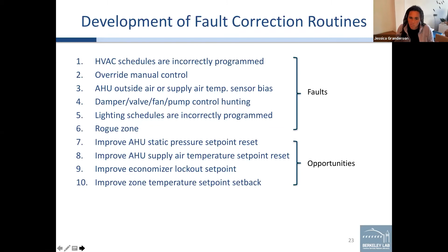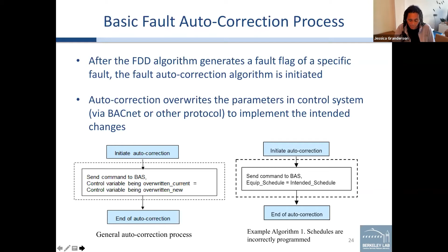This is just a schematic of what that process looks like in a sort of coded environment. The FDD tool finds a problem, raises a flag, which then triggers the correction routine to execute. That means overwriting specific parameters in the building control system—taking the old value, the logic tells us what the new value should be, and you write that back over the control system network.